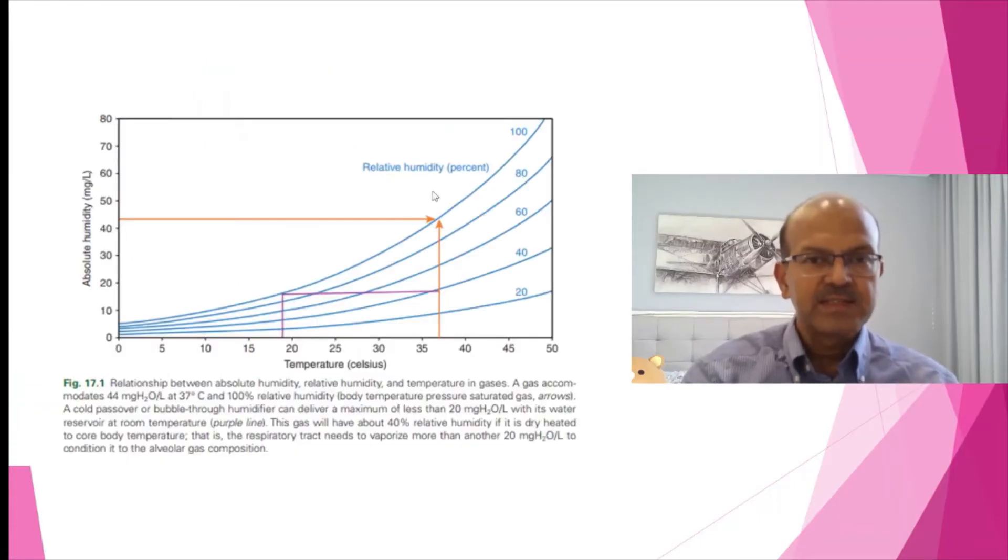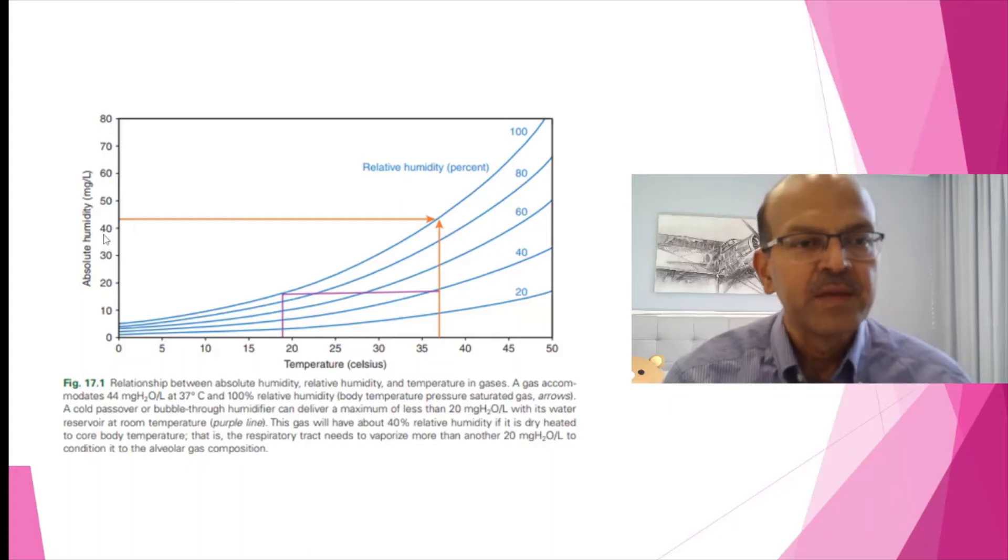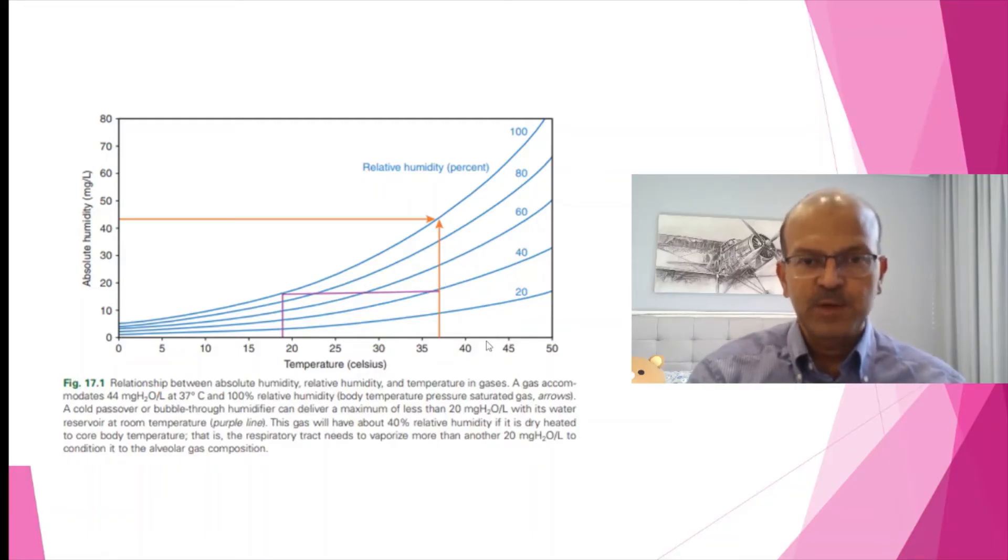So this chart illustrates the uptake of humidity according to the temperature. When you heat up the gas, the actual water vapor content that a gas can carry increases. So for the same absolute humidity, the milligrams of water that can be taken is increasing. The previous humidifiers allowed us to heat up to 40, 42 degrees at the humidifier level, and that allowed high water vapor to enter.